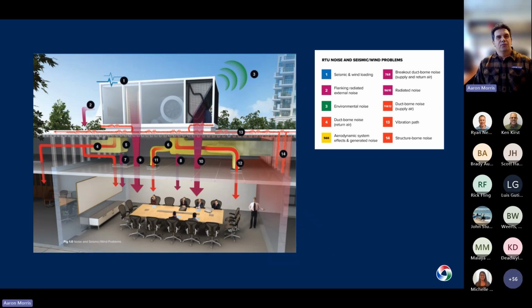So if we go back to those 4 transmission paths, we can see we've dealt with the ductborne noise and the breakout noise, which leaves us with the radiated and the vibration, right? A couple ways you can mitigate those noise paths would be to move the equipment further from your space. That'll help with the radiated noise. You could move it out so it's over the corridor, for instance. There are some drawbacks because you might have additional ductwork, which comes at a cost, and additional pressure drop, but that can be a good way to deal with the radiated noise.